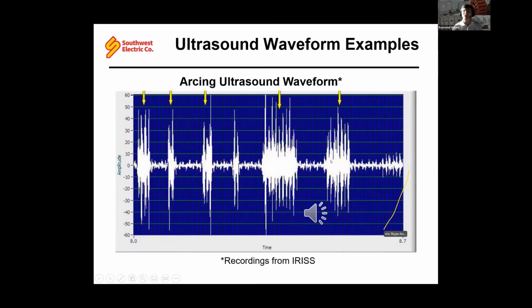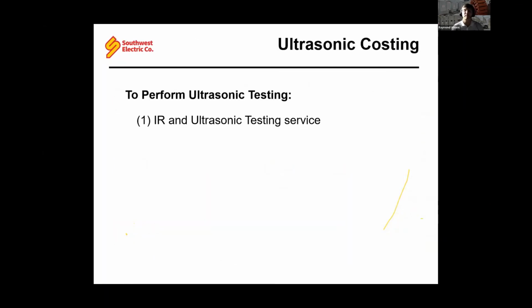So it's great that you can actually distinguish between those three electrical characteristics. And again, all this is done while energized. So to do this testing, you would need your IR and ultrasonic testing service. You can buy your own equipment if you want to, or you can just have it done for you, just like you would an oil sample. And for that testing service, it's usually fairly cost effective.